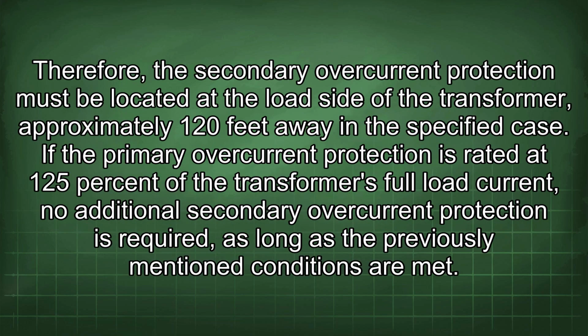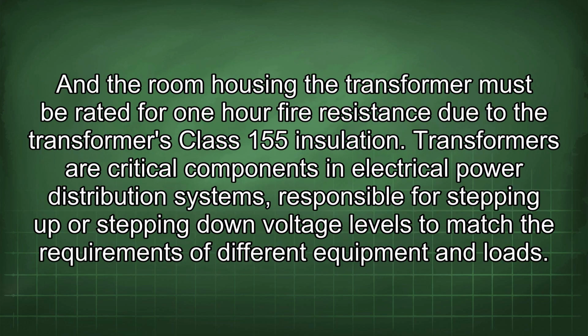Therefore, the secondary overcurrent protection must be located at the load side of the transformer, approximately 120 feet away in the specified case. If the primary overcurrent protection is rated at 125% of the transformer's full load current, no additional secondary overcurrent protection is required as long as the previously mentioned conditions are met. And the room housing the transformer must be rated for 1 hour fire resistance due to the transformer's class 155 insulation. Transformers are critical components in electrical power distribution systems responsible for stepping up or stepping down voltage levels to match the requirements of different equipment and loads.